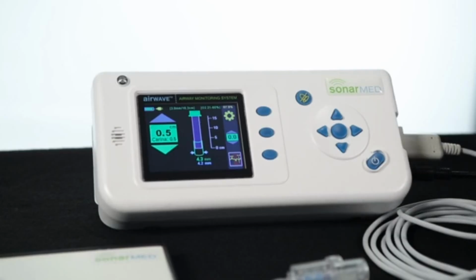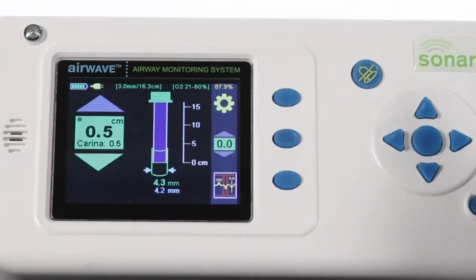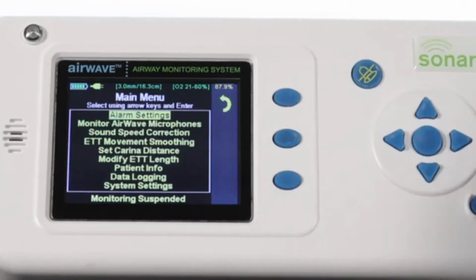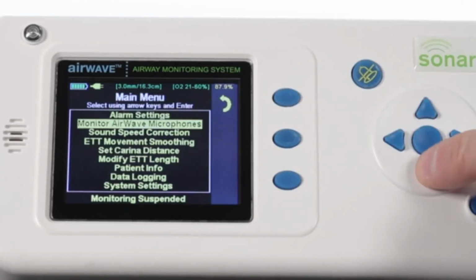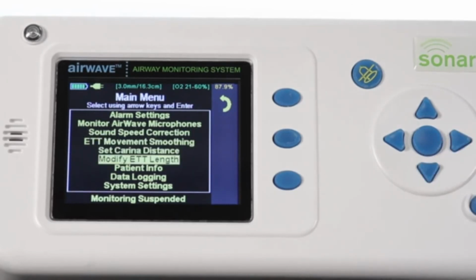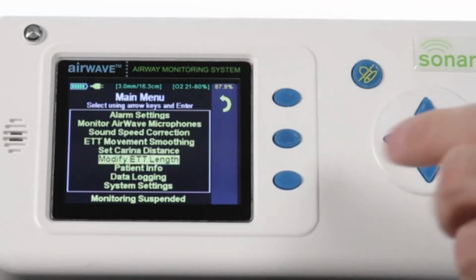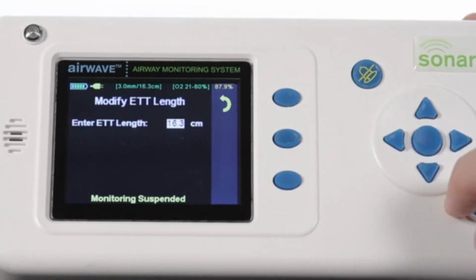The second thing we can do with the SonarMed airwave monitoring system on setup is to modify the length of the endotracheal tube. It's not uncommon for some neonatal intensive care units to cut or reduce the length of the endotrach tube, and we have to adjust the monitor when that's done. To do that, we hit the button to the right of the gear, use the downward arrow key to get to the Modify ET tube length. We hit the center to enter button.